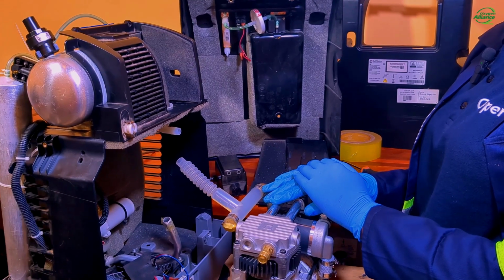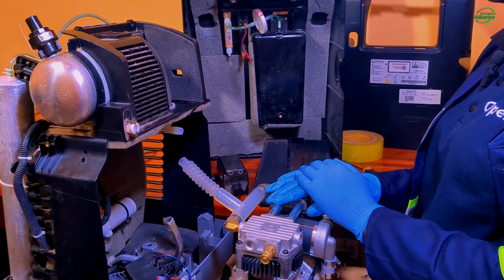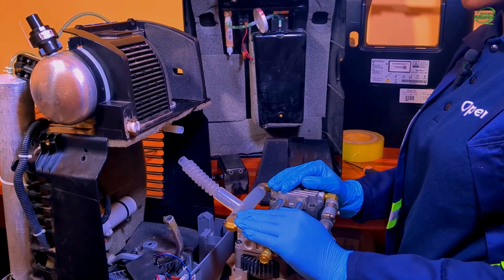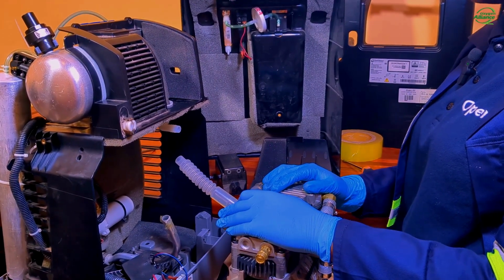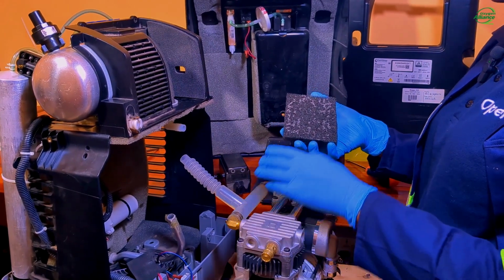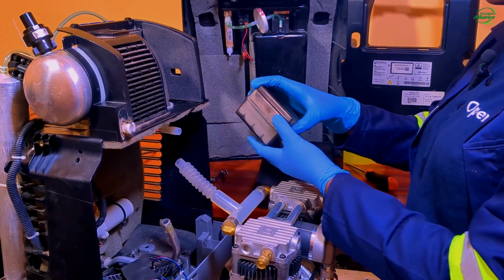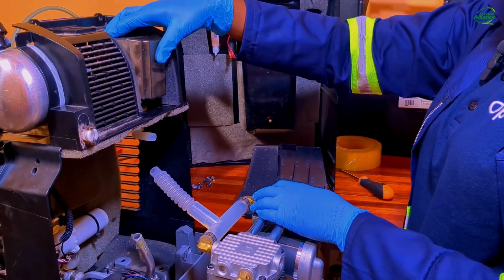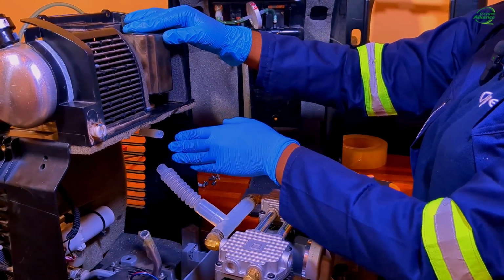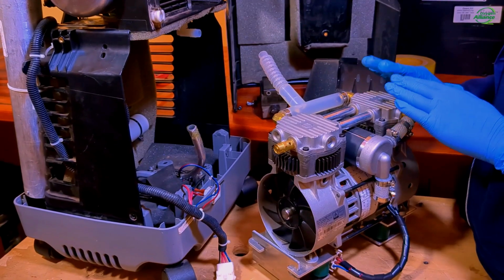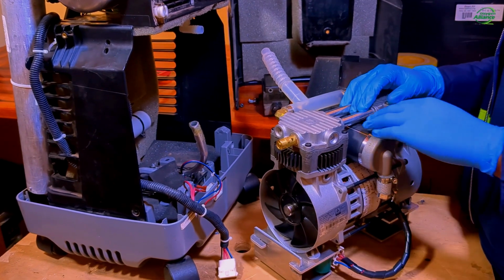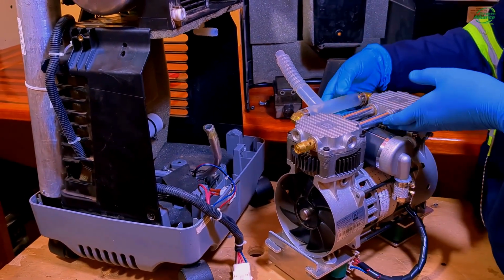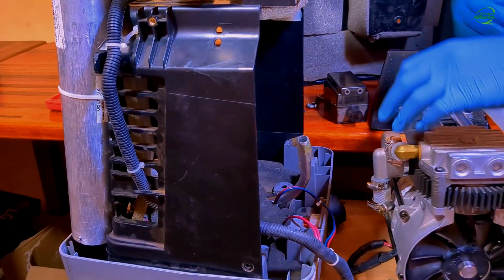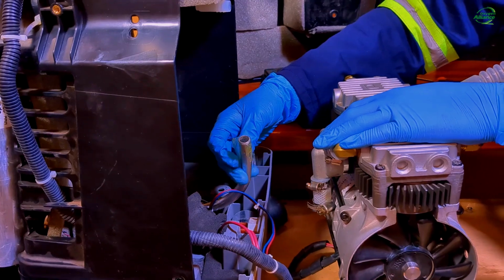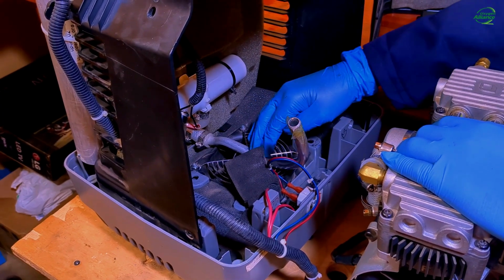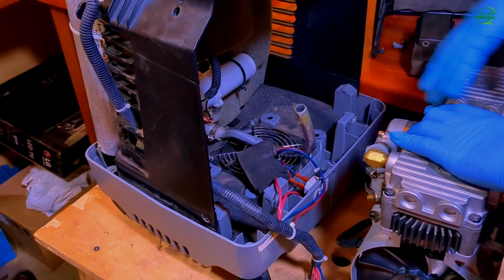So moving on, I will explain to you the pneumatic system for the 1025 oxygen concentrator. So when you switch on your concentrator, the compressor takes in air from the environment. So the air first passes through the gross particle filter before it is taken to the fine particle filter, which is located over here. And from the fine particle filter, the air then passes through this tubing to the compressor. So after the air is compressed, it is filtered through this compressor filter and taken out through this tubing, which is connected here. So this is the heat exchanger tube. This heat exchanger tube takes the air over the fan and to the rotary valve.